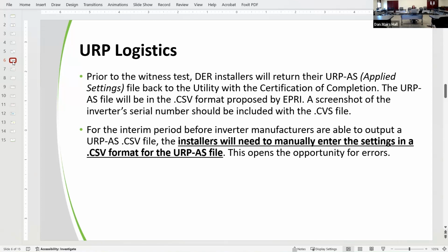if they're able to Bluetooth into the inverters so you can actually see those settings. Key ones to look at, in my mind, is a lot of the technical requirements today are now requiring volt-var power control instead of power factor. So that might be one to say, okay, show me that power factor is disabled and volt-var is enabled. You don't necessarily need to go through all the different set points after that.